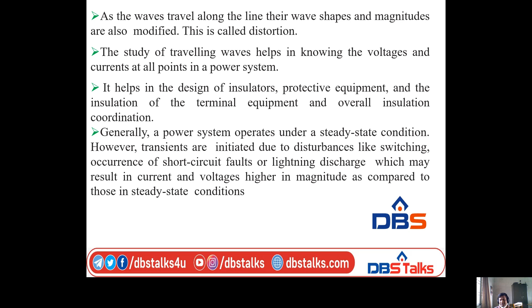Generally, a balanced three-phase power system operates under steady state conditions. However, practically it is not possible. Some transients are initiated due to disturbances like switching surges, lightning surges, and the occurrence of short circuit faults. All these, switching surges, short circuit faults or lightning discharges, may result in current and voltage disturbances, that is, higher magnitudes compared to the steady state value. It may reach very peak values, enormously increasing the voltage magnitude, which may damage the protecting equipment in the substation.